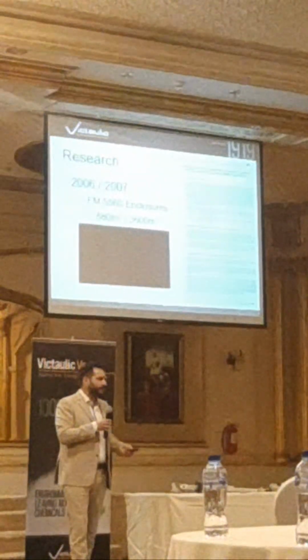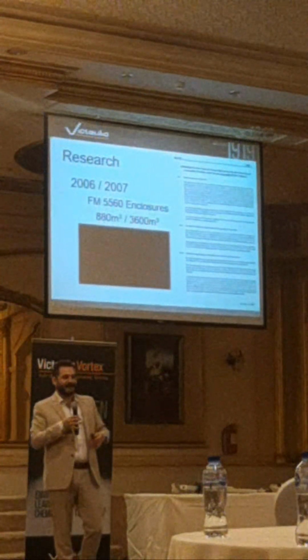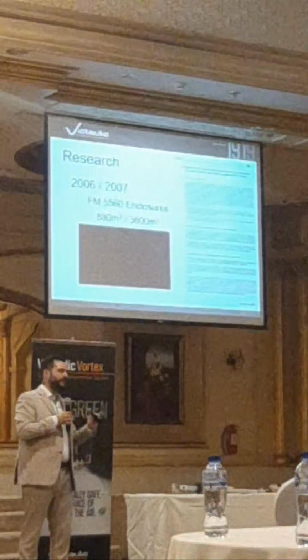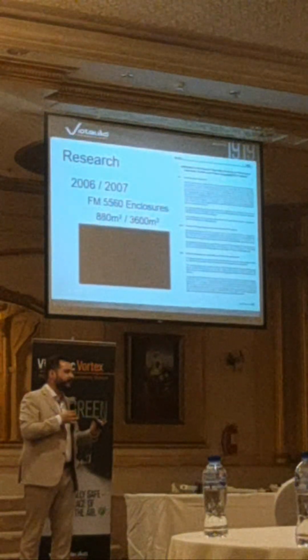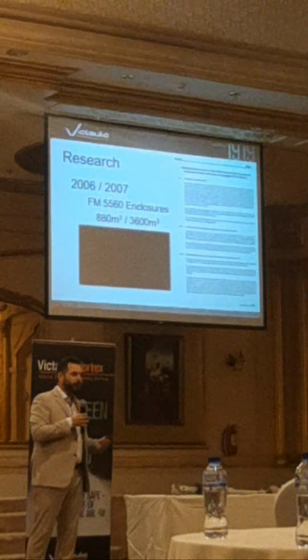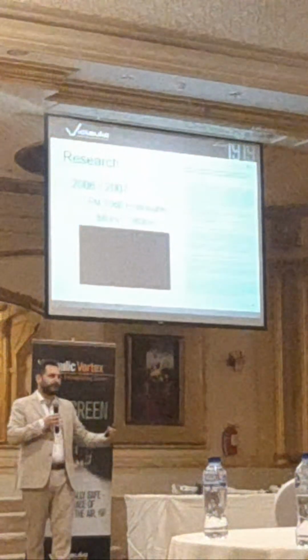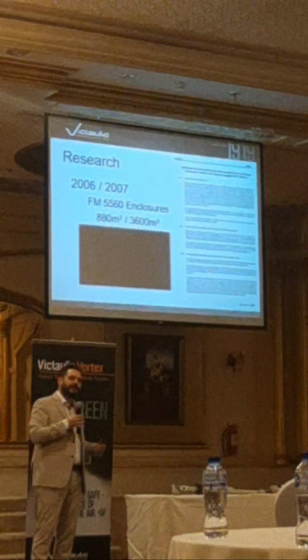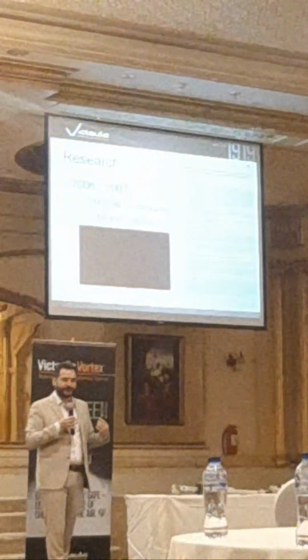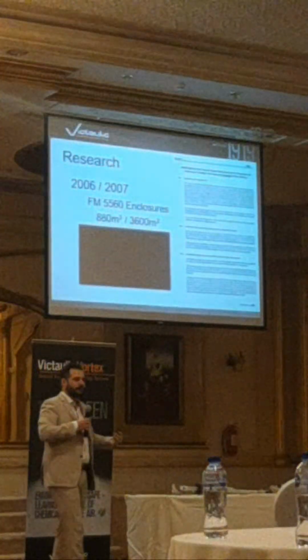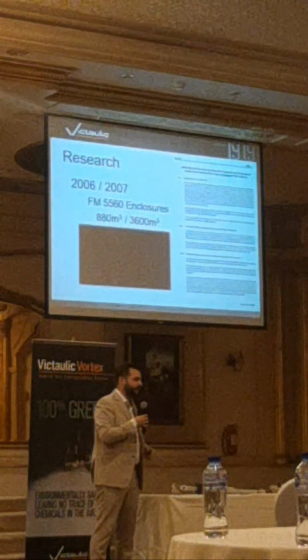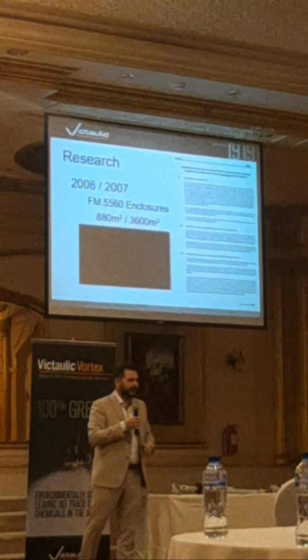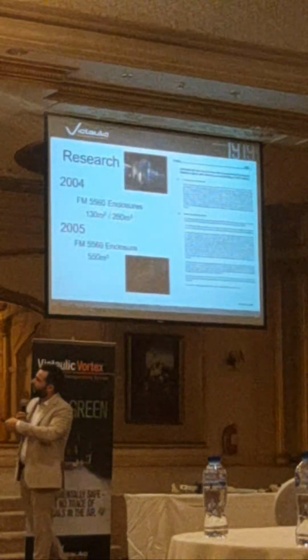What I'm aiming at is that the FM approval we have is limited to 300 cubic meters. That's not that large, but that was the room we tested in with FM. Does it mean it won't work with 600 cubic meters? Not precisely, but you can just add another zone.